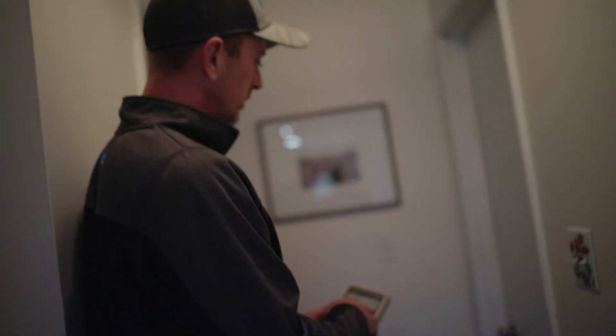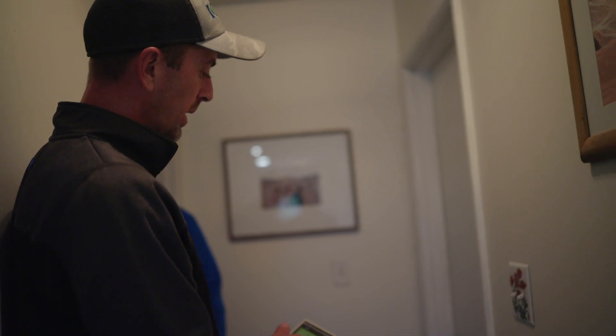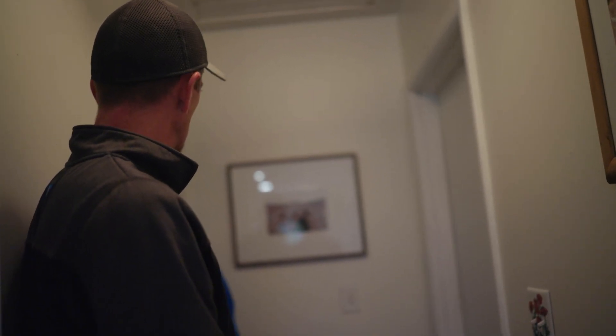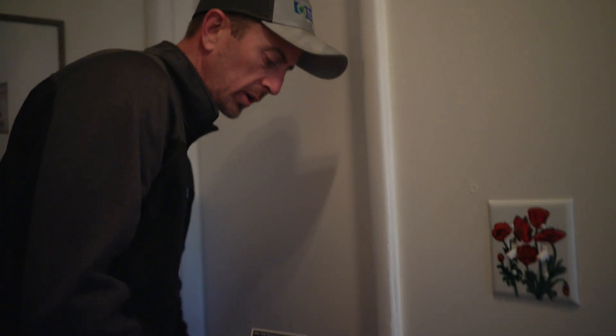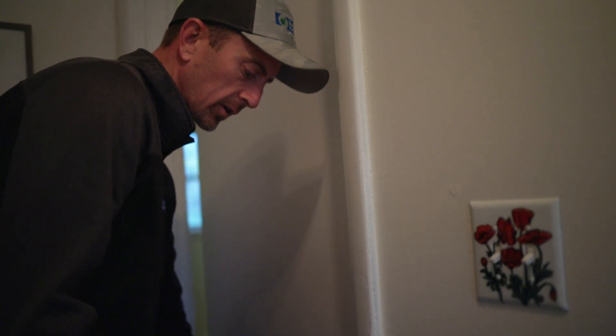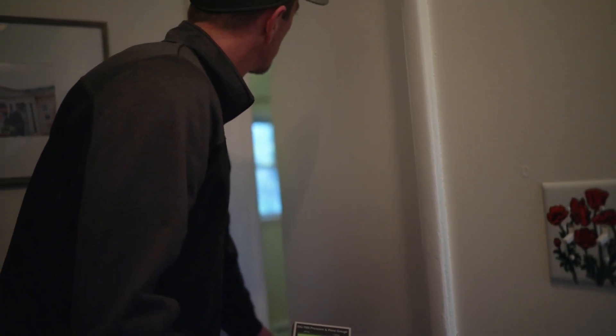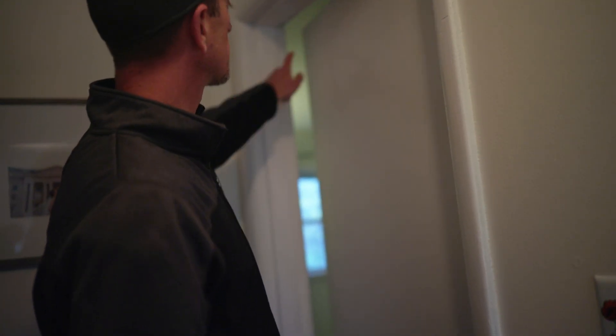We're doing a pressure differential test with the heating and cooling system running right now, going into the master bedroom with the door shut. What you're looking at is the pressure between the common area of the house and that bedroom with the door shut — I want that number to be as close to zero as possible, meaning equal pressure, with equal air going in and coming back out. Right now it's a 10 pascal pressure difference. To put that into perspective, an Energy Star Home requires a pressure difference of less than two. So we're way off. The easy way to see how much of an opening you need is to slightly open the door until that number hits zero, and then measure that gap — it works out to about two and a half to three inches on a six-foot-eight door.